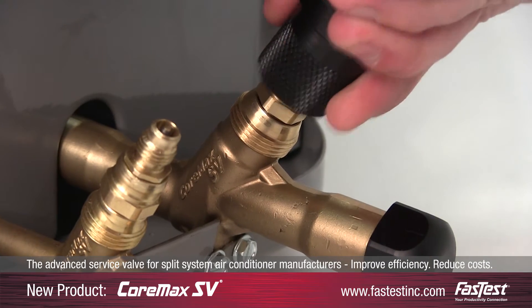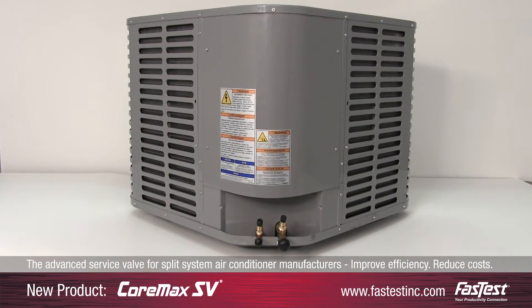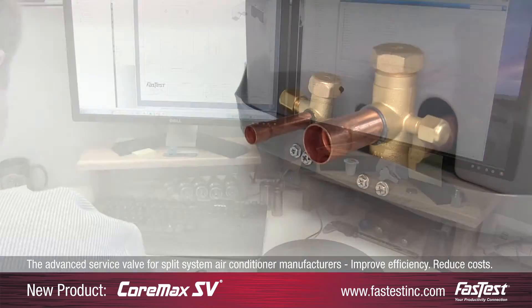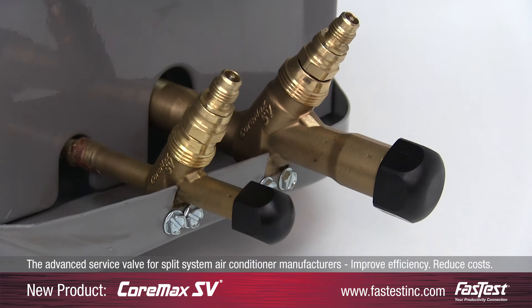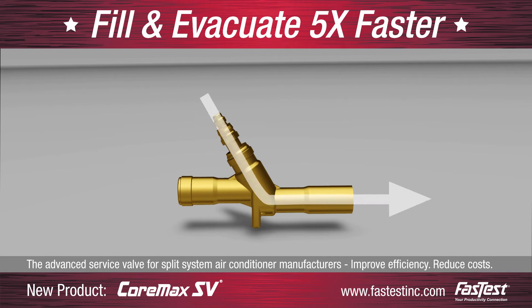Designed for speed, efficiency, and accessibility, the CoreMax SV is a direct replacement for conventional service valves. Our goal was to address the common leak points in Schrader and other outdated service valve products. CoreMax SV eliminates refrigerant loss and significantly improves system integrity. Engineered with the advantages of Fastest's industry-leading access valve, the CoreMax SV allows manufacturers to fill and evacuate up to five times faster.